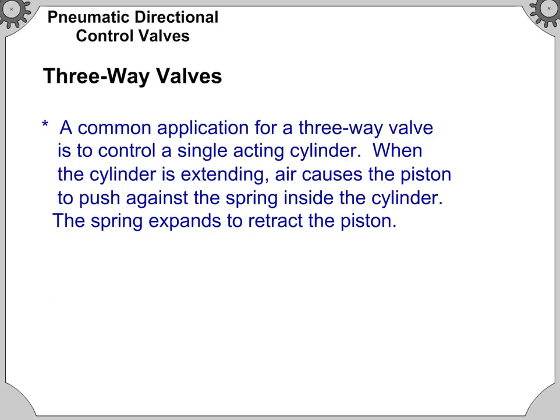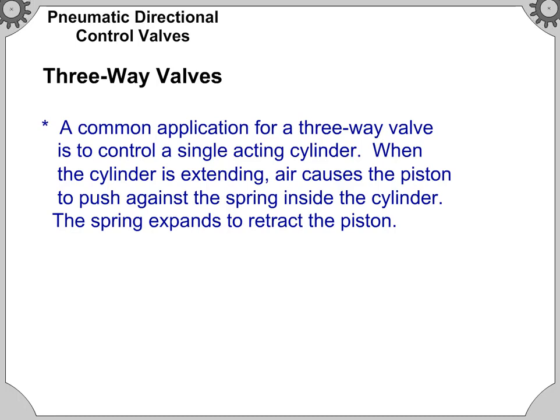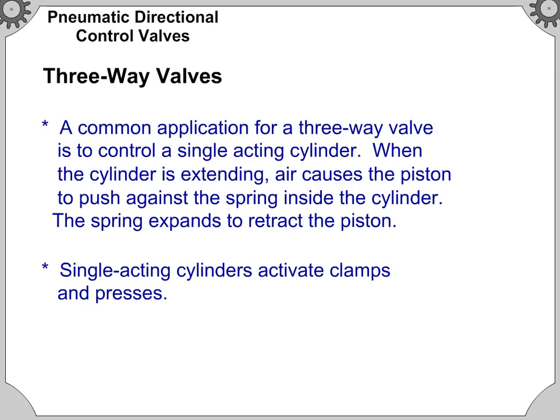A common application for a three-way valve is to control a single-acting cylinder. When the cylinder is extending, air causes the piston to push against the spring inside the cylinder. The spring then expands to retract the piston. Single-acting cylinders activate clamps and presses.